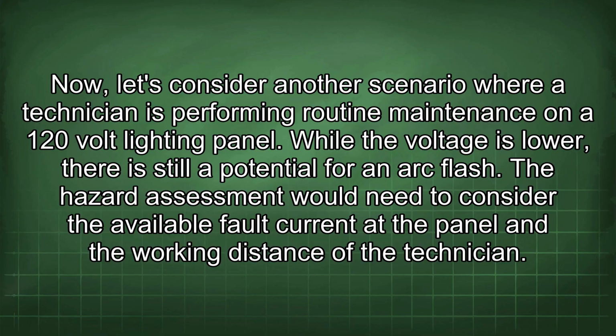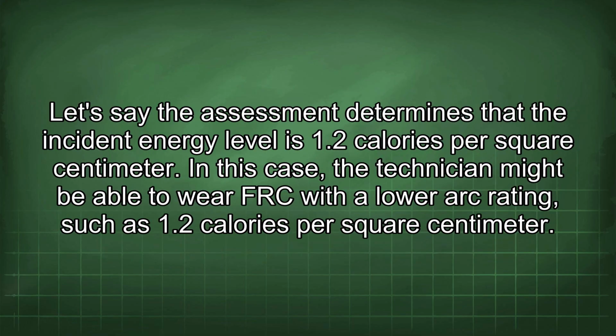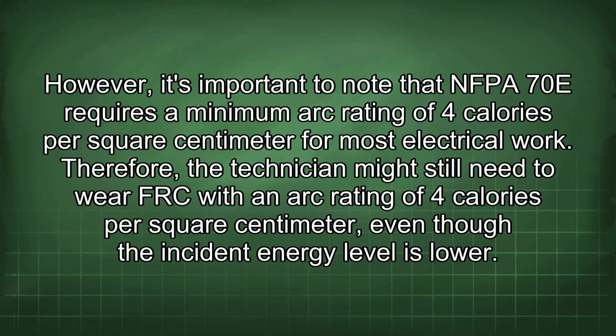While the voltage is lower, there is still a potential for an arc flash. The hazard assessment would need to consider the available fault current at the panel and the working distance of the technician. Let's say the assessment determines that the incident energy level is 1.2 calories per square centimeter. In this case, the technician might be able to wear FRC with a lower arc rating such as 1.2 calories per square centimeter. However, it's important to note that NFPA 70E requires a minimum arc rating of 4 calories per square centimeter for most electrical work. Therefore, the technician might still need to wear FRC with an arc rating of 4 calories per square centimeter, even though the incident energy level is lower.